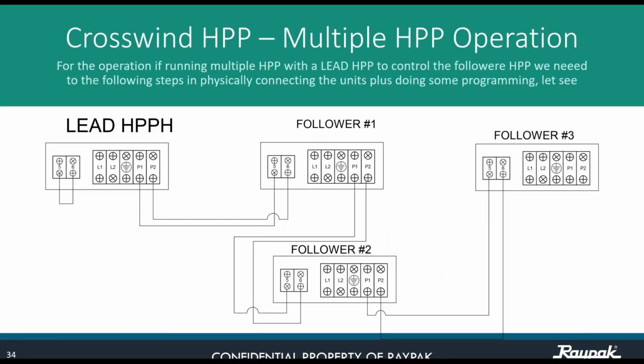Also, we can run multiple heat pumps. For that operation, there has to be a lead heat pump to control the follower heat pumps. We need to follow some steps connecting the units, plus doing some programming. So let's do the physical connections first. You see right here 5 and 6. This is for automation. L1, L2 is for high voltage coming from the main service panel. This is ground, and then you have P1 and P2.